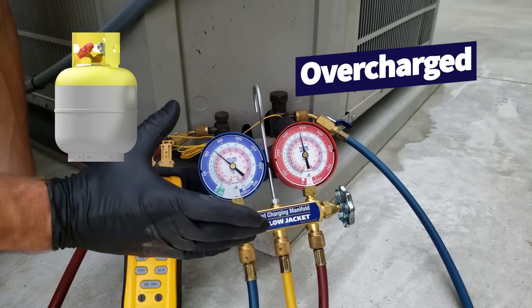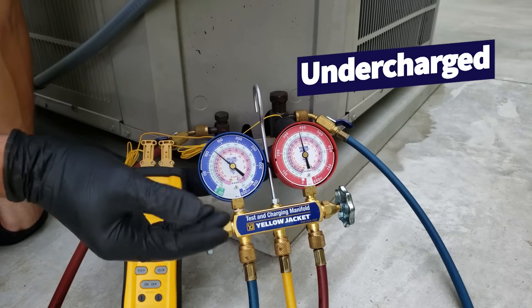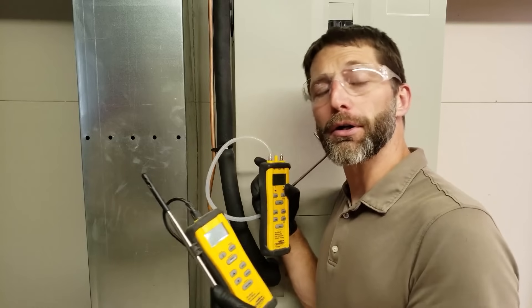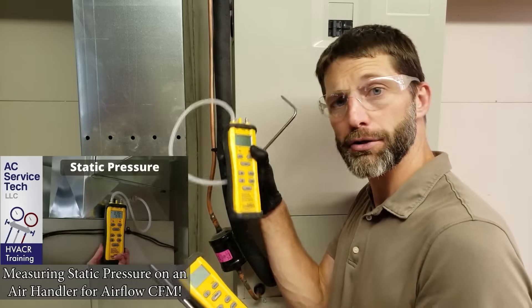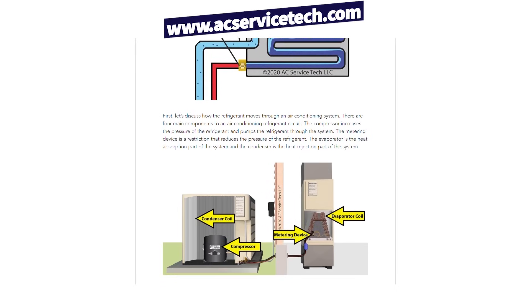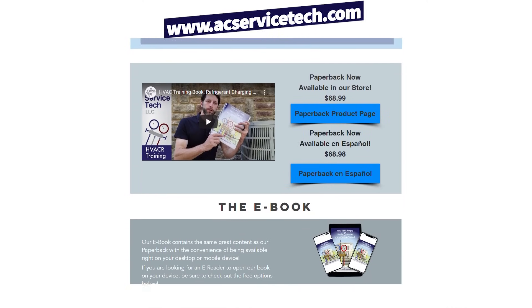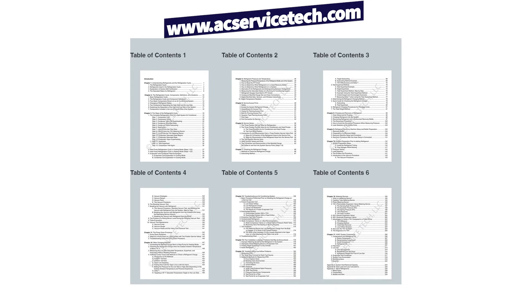If the system is overcharged, you'd have to remove refrigerant out of the liquid line while the system is running. If the system is undercharged and needs refrigerant added, you put it into the low side of the running system. There's a lot involved with checking the charge, and you even want to check the airflow before you get started. Check out the free articles at acservicetech.com — we cover the subcooling method, the total superheat method, and operating pressures. We also have a refrigerant charging and service procedures book for air conditioning available on our website and on Amazon at acservicetech.com/acbook.